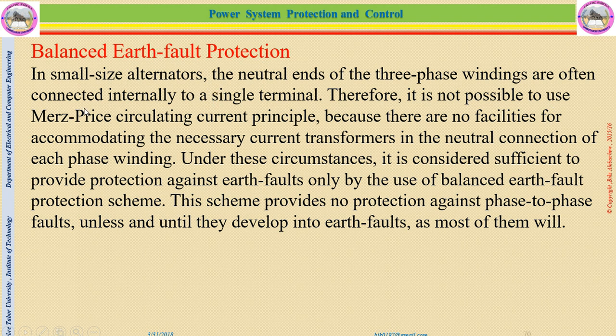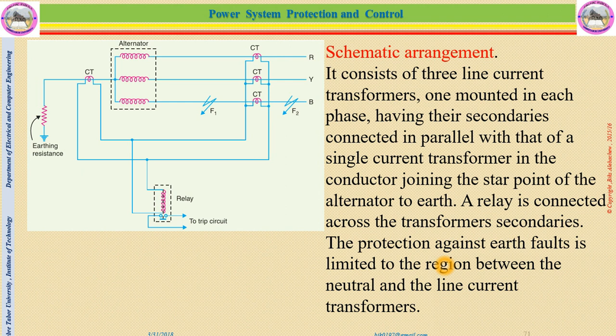Therefore, it is not possible to use the circulating current principle because there is no facility for accommodating the necessary current transformers in the neutral connection of each phase winding. Under the circumstances, it is considered sufficient to provide protection against earth fault only by the use of a balanced earth fault protection system. This system provides no protection against phase-to-phase faults unless and until they develop into earth faults, as most of them will. So until the other protection mechanism operates, it cannot protect against phase-to-phase faults, but it is secure for earth faults only.